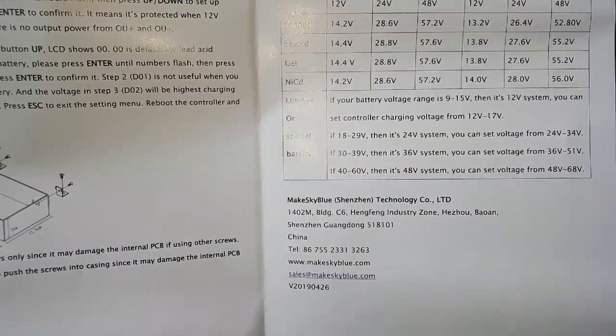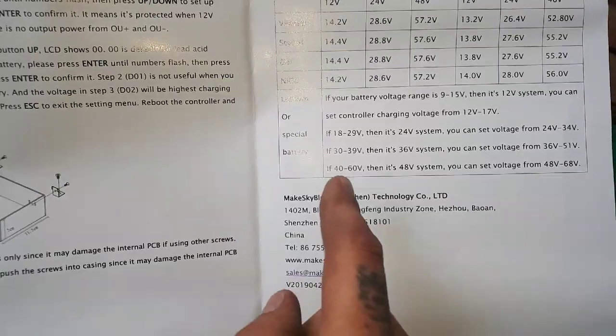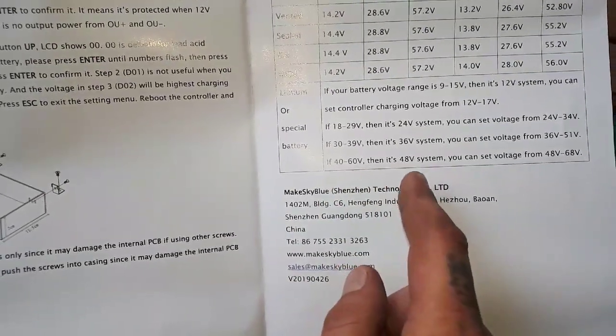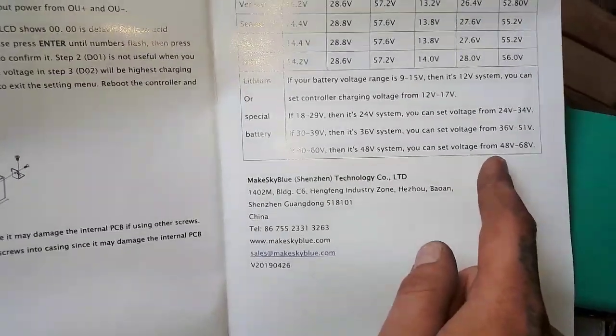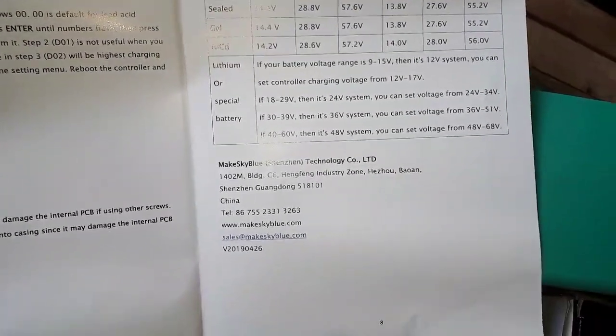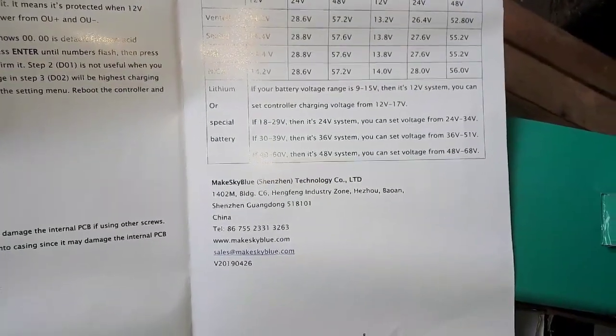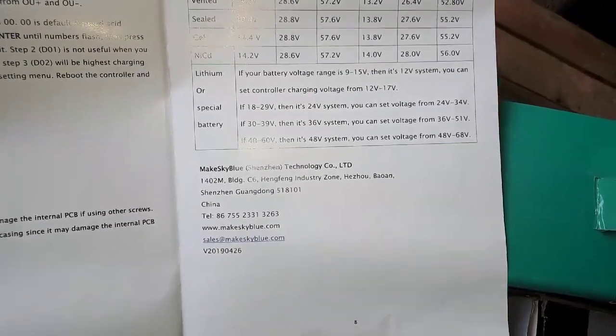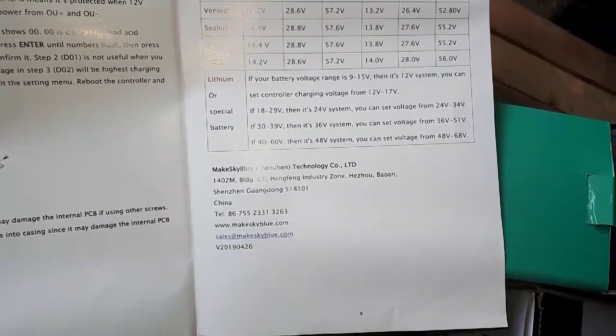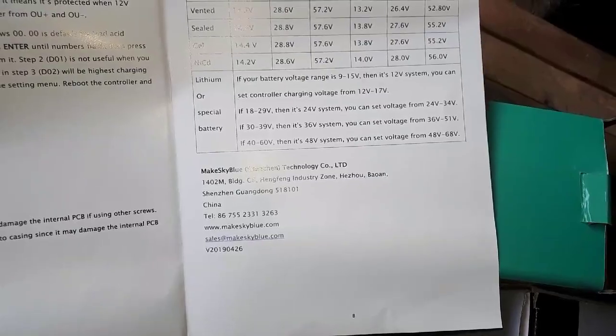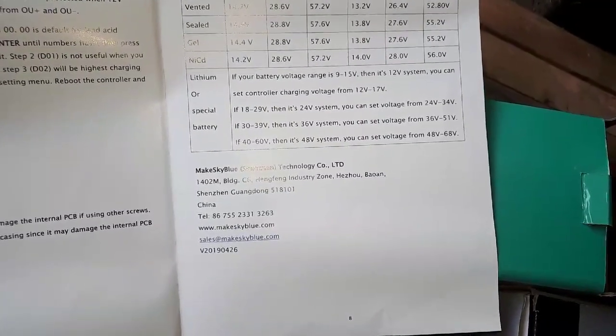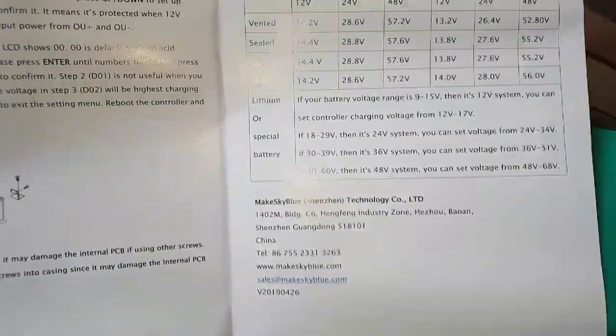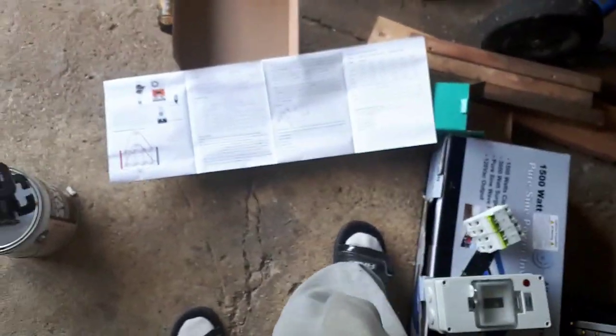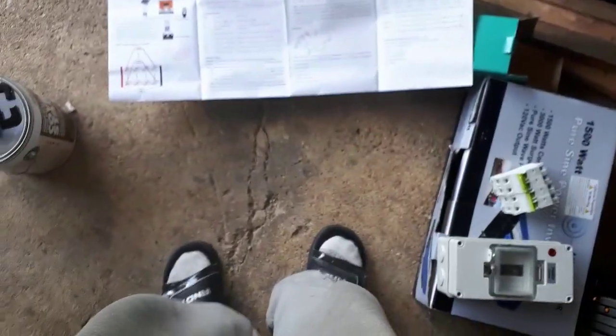If your battery is between 40 and 60 volts, that's a 48 volt system, then you can adjust your parameters from 48 to 68. You can also adjust that on your absorb and on your float. It'll do the absorb for an hour, then switch down to float automatically. But you can also set your float to the same as your absorb, so it does both at the same time. That's what you usually do for this type. If you don't need to float, you just set it for 1 voltage and you're good to go.